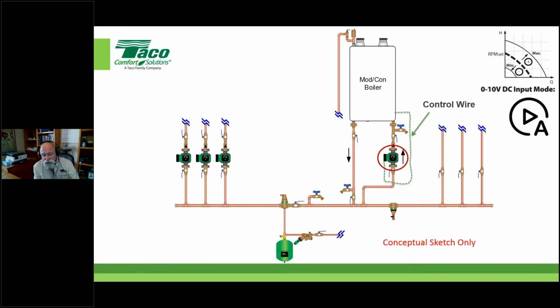The problem I see out there, especially with some products that come packaged with some competitor product, is there's an old saying: you can't go any lower than low. If you put a circulator on there that has 0 to 10, but is physically too big for the job it's being asked to do, then it just sits there on low speed. It can't go any lower, and therefore it cannot widen that delta T any more than low speed. A lot of you know where I'm going with that, but maybe I should open it up if there are any questions. And if not, I'll continue on.